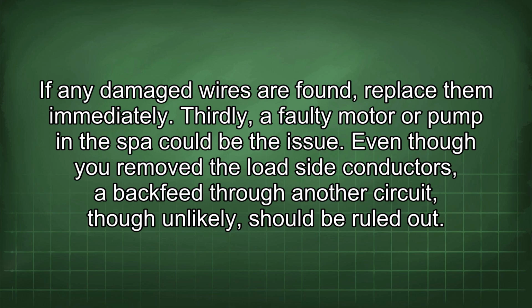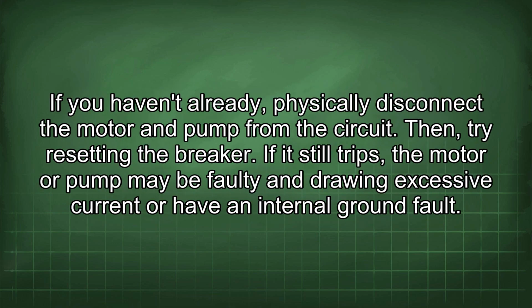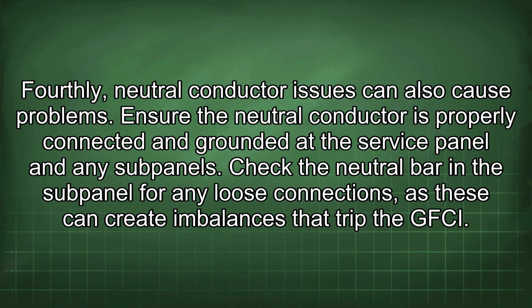Thirdly, a faulty motor or pump in the spa could be the issue. Even though you removed the load side conductors, a backfeed through another circuit, though unlikely, should be ruled out. If you haven't already, physically disconnect the motor and pump from the circuit. Then try resetting the breaker. If it still trips, the motor or pump may be faulty and drawing excessive current or have an internal ground fault.